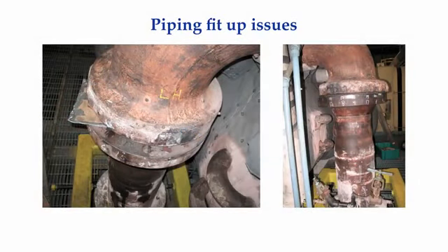I'm not sure what people want me to say about this. If our piping is misaligned by 2 or 3 inches, you are going to have to cut and refit the pipe. If the piping is somewhat close to being aligned but off by less than 1/4 of an inch, there are ways we can possibly account for this when aligning the machinery. Dealing with small amounts of piping fit-up problems will be addressed in the intermediate alignment tutorials.